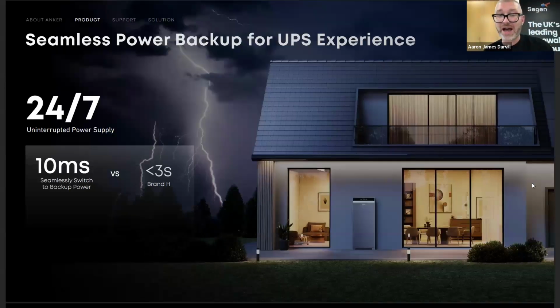We also have seamless power backup, so again it's about educating the client. We hear this all the time, where an end user will think they're going to have unlimited power supply, and we both know that's not necessarily the case. It's about what's in the battery, and being cautious and clever with their time of use or what appliances they've got on within the house. You have the option that if there's 15 kilowatt hours in the battery, it will supply that if there's a backup or power backup needed. Or you could support with a sub panel to easily cover those critical loads. So just plan that project accordingly.